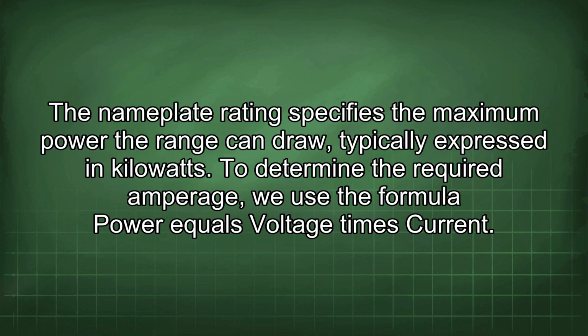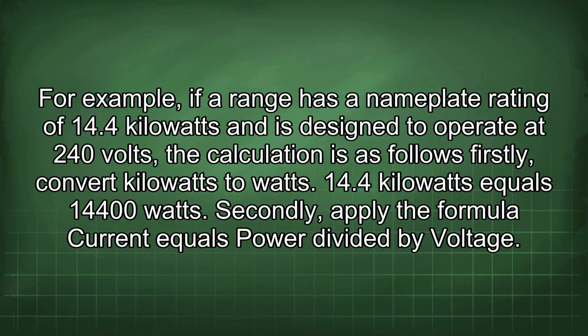To determine the required amperage, we use the formula power equals voltage times current. For example, if a range has a nameplate rating of 14.4 kilowatts and is designed to operate at 240 volts, the calculation is as follows. Firstly, convert kilowatts to watts. 14.4 kilowatts equals 14,400 watts.